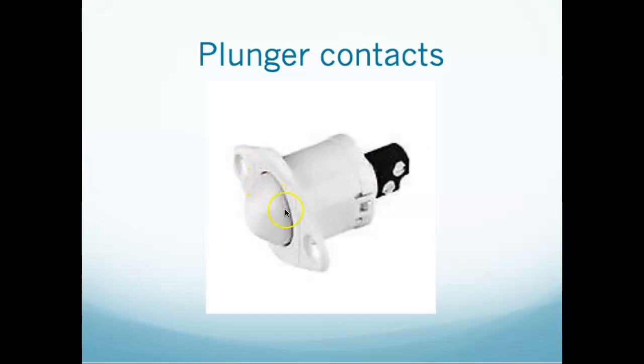It's a single-sided device. You don't have one on the door and one on the frame. You can just use it on the frame. The springs tend to wear out in these, so you don't see plunger contacts used on anything that's a door that's really heavily used. You wouldn't see this on a main entry door anywhere. These things can get damaged pretty easily. But on things like a drawer or a cabinet where you're storing things, where you're only opening it maybe 5-10 times a day, these are pretty good. Not a bad idea. And sometimes the best application to use.